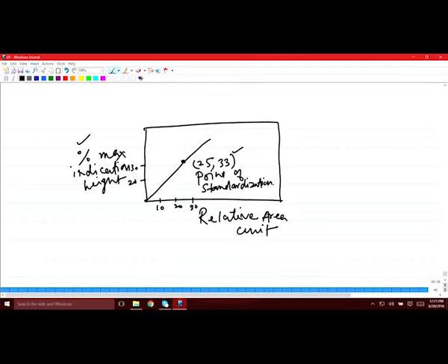And then you see the rest of the points, where they are falling, whether they are falling on this curve, or if you note any deviation, you simply have to note that deviation for a particular hole size, and when you do the test, this is the correction that you need to provide for that particular size.